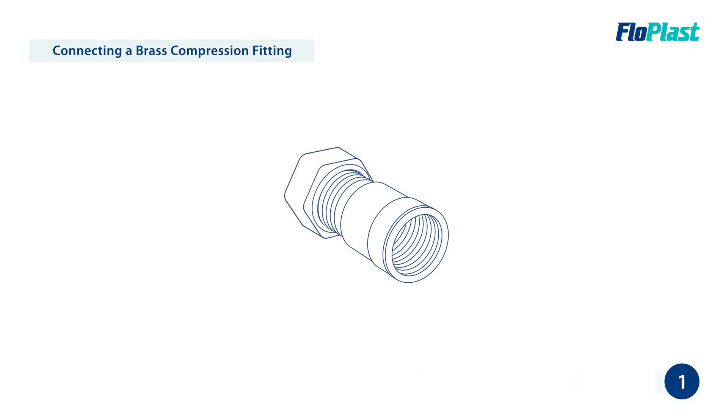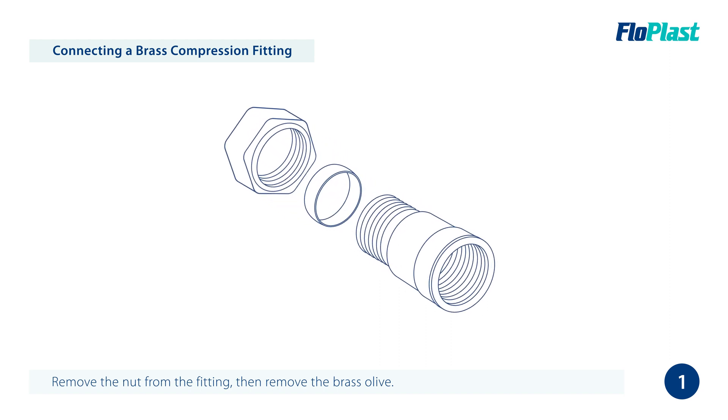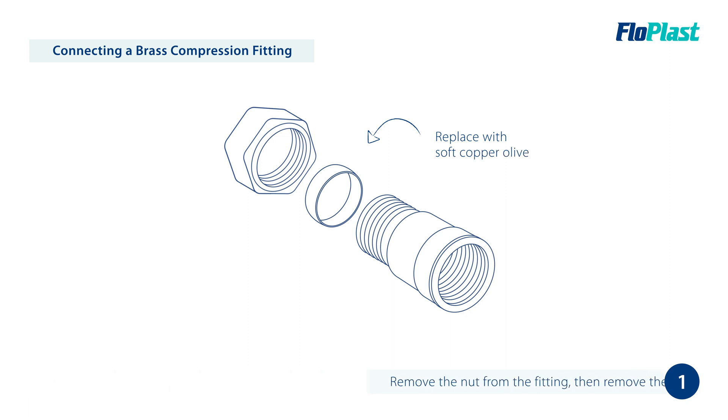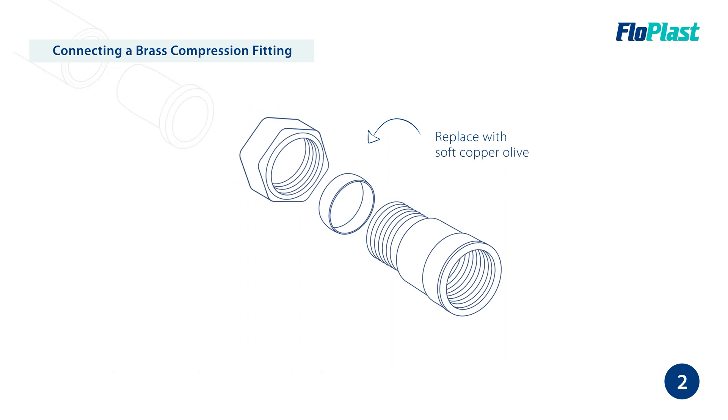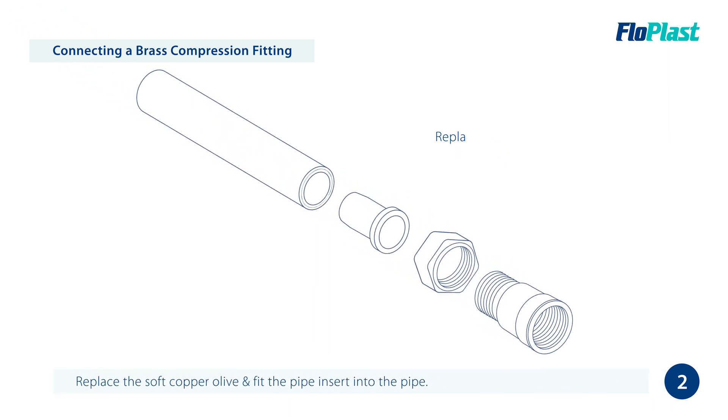When installing the pipe to a brass compression fitting, to begin with, remove the nut. You then need to remove the brass olive. Note that to connect to a brass copper fitting, a soft copper olive must be used. Within the brass fitting, replace with the soft copper olive.